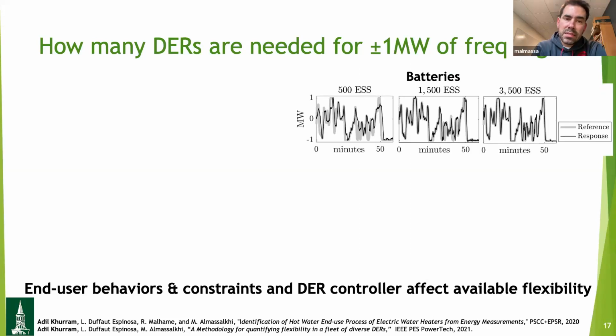Even something as simple as taking 500 batteries to track a frequency regulation signal is not super straightforward. 500 batteries perform differently than 1,500 batteries, and differently than 3,500 batteries, in terms of tracking a plus or minus 1 megawatt frequency regulation signal. So if you get paid for performance, you have to think about how many devices you need to earn sufficient credits for a 1 megawatt capacity payment from frequency regulation.